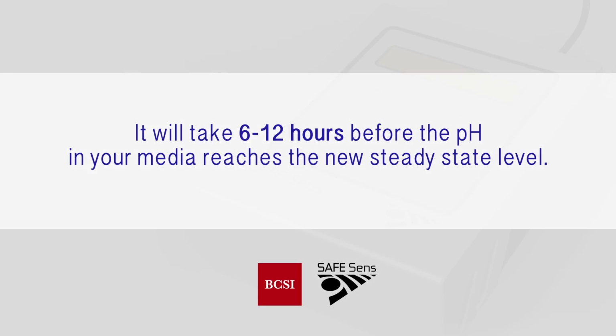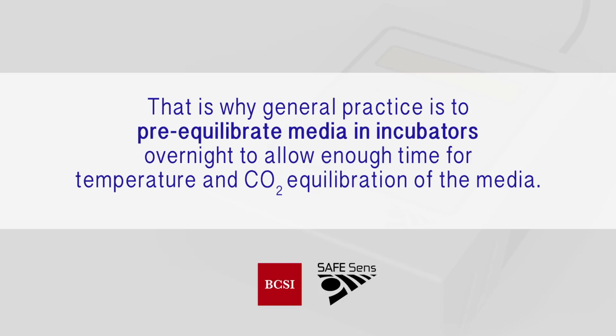development. It is important to be aware that changes to your incubator settings, such as adjusting the CO2 level from 5 to 6%, will not be immediately detected through the SafeSense system. It will take 6 to 12 hours before the pH in your media reaches the new steady state level. This is due to the slow rate that CO2 is able to absorb through the oil and into the media in the pH sensor. That is why general practice is to pre-equilibrate media in incubators overnight to allow enough time for temperature and CO2 equilibration of the media.